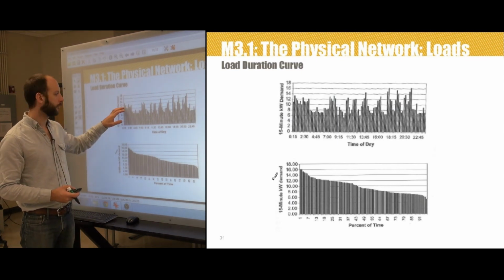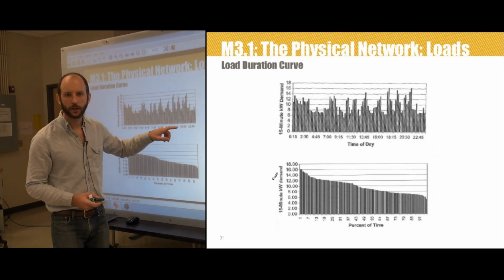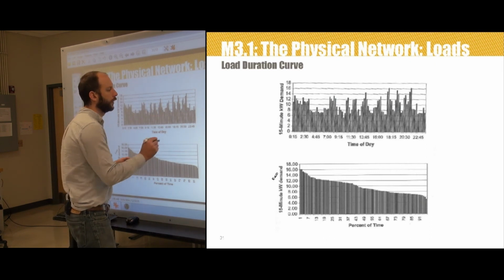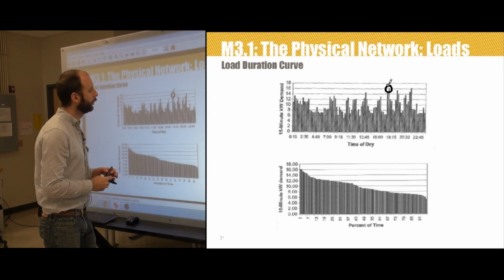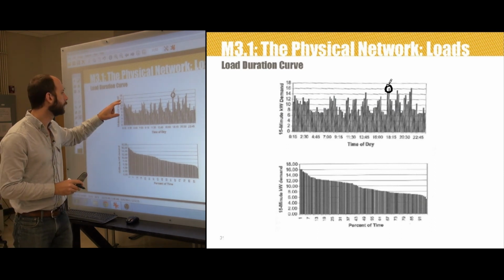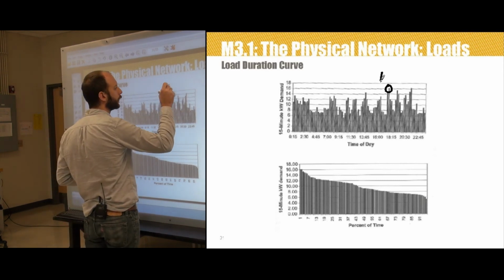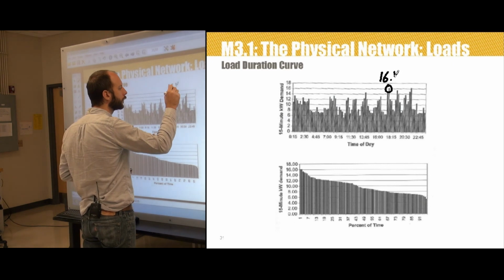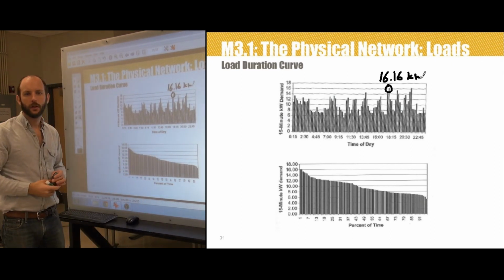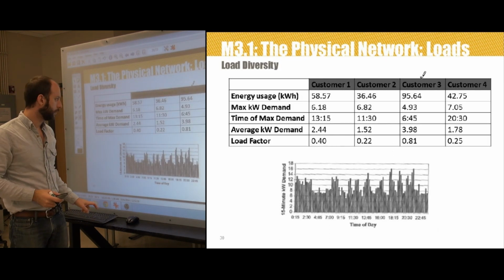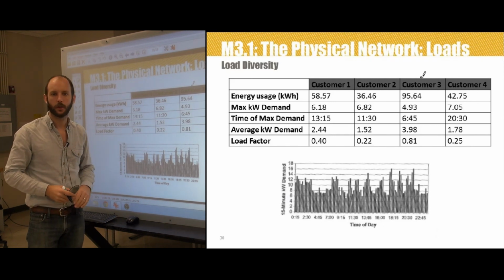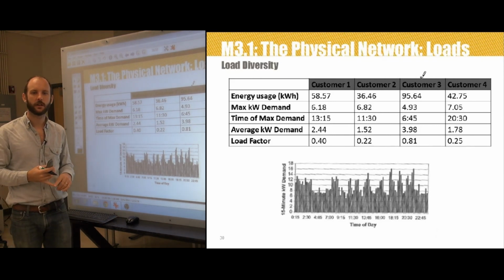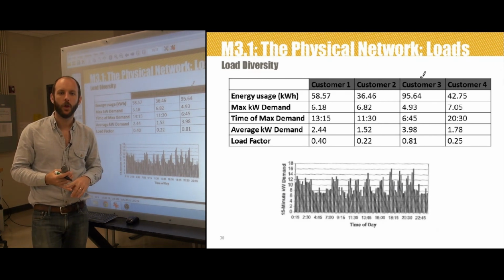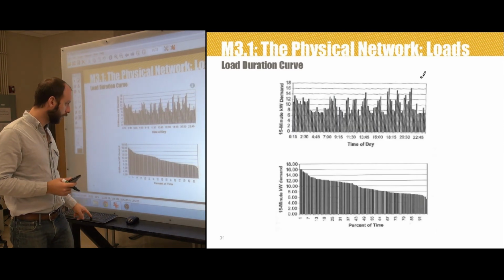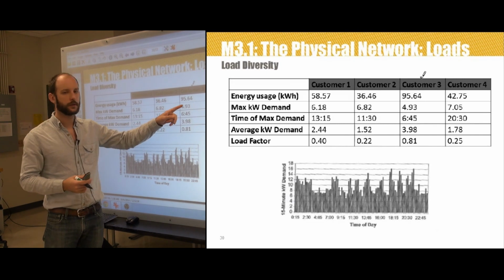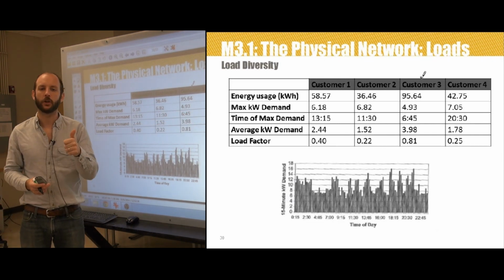So we can see that the 15-minute maximum diversified demand here looks like it's occurring right about here at 17:30 or 5:30 in the afternoon. And it's got a value of a little bit more than 16 kilowatts, 16.16 kilowatts is what I have written down for that. That max demand and time doesn't correspond with any of these times, right? The maximum diversified demand does not necessarily occur at the same time as any of the individual maximum demands, nor is that maximum demand there the sum of these max demands, right? We have to consider both the magnitude and the time.